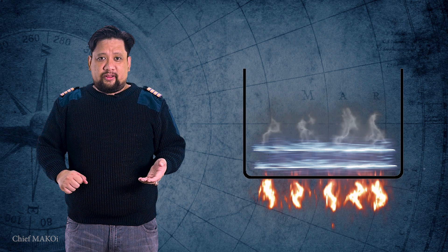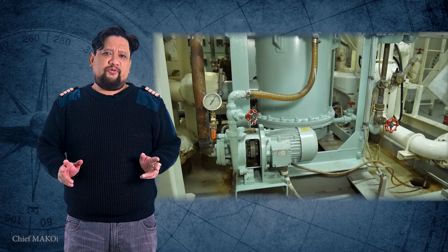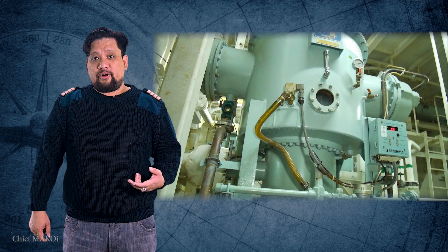Now if we cool down steam, it will condense and turn into distilled water, which theoretically should be pure H2O, otherwise known as freshwater. Obviously ships need to do this on a large scale, and distillation plants on board cargo ships are typically designed to produce somewhere between 15 to 50 tons of freshwater per day, sometimes more depending on the ship type and freshwater requirements.